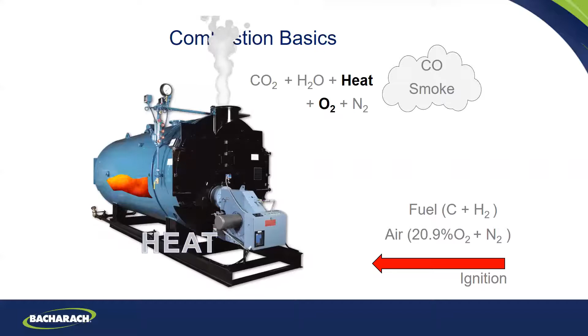So we talk about CO2, water vapor, heat, oxygen, nitrogen in the stack, and possibly carbon monoxide. Hopefully no smoke. But the two elements we want to look at here are the oxygen and the heat, and this is what's going to give us our combustion efficiency. So we have an oxygen sensor in our combustion analyzer that's going to measure that oxygen. We have a thermocouple in our probe that's going to measure the temperature in that stack. And then inside of our combustion analyzer, we have our thermistor that measures the room temperature. So it subtracts that room temperature from the stack automatically, takes the oxygen reading, and it calculates combustion efficiency for you. We'll go over how to do that later on.